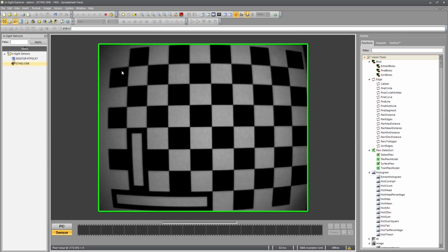and put under the camera, there's a significant fisheyeing effect, which means that each of these lines, while they are the same length in reality, once they're captured by the image plane in the camera, are significantly distorted. And now, this length over here is going to appear shorter to the camera than this length here. Fortunately, COGNEX has included with their software a package that helps us do nonlinear calibration to get past that effect.